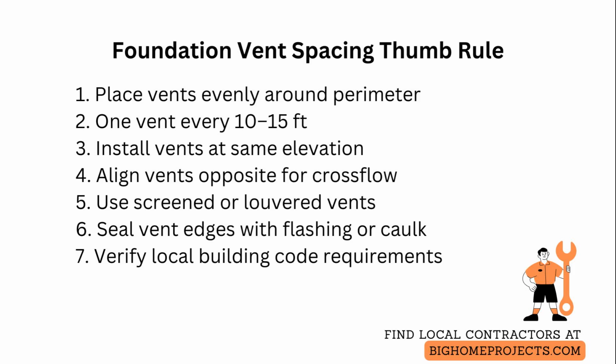For typical crawl spaces, we recommend roughly one vent every 10 to 15 feet based on foundation height and ambient conditions, with closer spacing for larger or irregularly shaped areas. Measure the total perimeter and divide by your chosen spacing to determine exact placement.